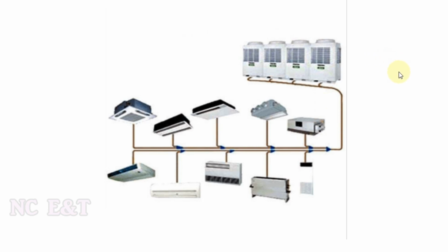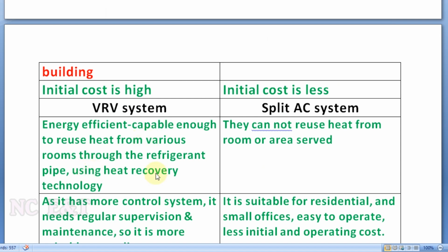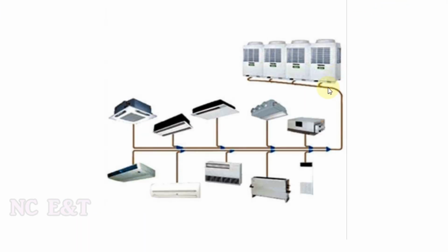Another characteristic is that some of the indoor units of a VRF circuit we can use for heating and some of the units we can use for cooling simultaneously, and we call this technology heat recovery technology. It means if we are using one circuit of the VRF system and we need cooling in some rooms and heating in some rooms, we can use one circuit for both heating and cooling.